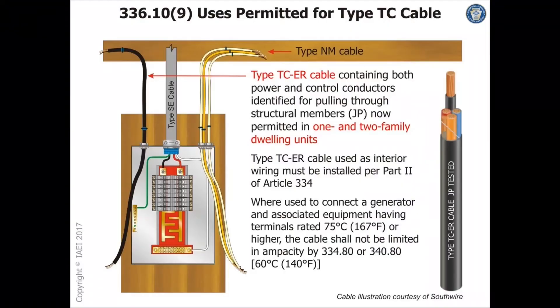Type TC cable is seeing some new applications. It's now going to be allowed to be installed exposed without a raceway in dwelling units. That brings to nine the number of uses permitted for TC cable.